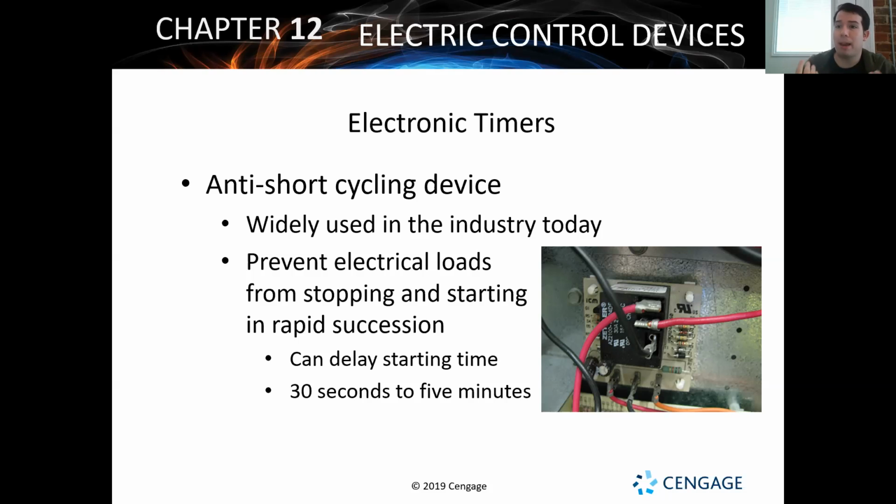So to prevent that from happening, these typically look at the amount of amperage, they look at the amount of magnetism that's left in the system, and until it drops down, it's not going to allow power to come back into it. Because the last thing you want is a motor that was just turned off, turned on again. That's like taking a car, starting it, turning it off, starting it again, turning it off, starting it again. That's ridiculous. That's a waste of energy. That's a whole lot of battery power you're using, a whole lot of fuel you're using, and you're wearing down the motor, because startup is one of the biggest things that's going to wear down an engine or a motor.